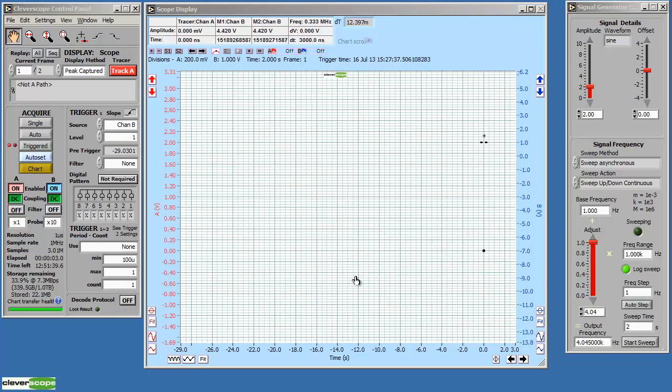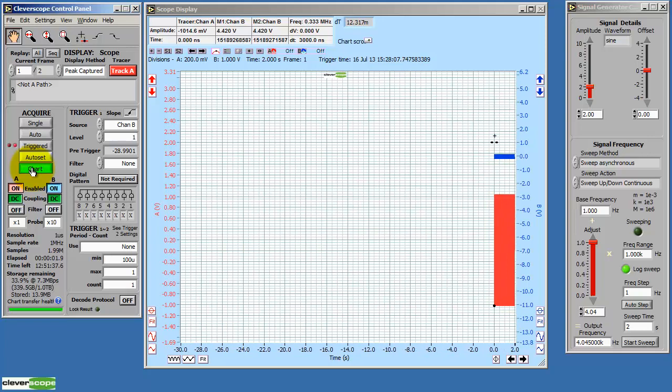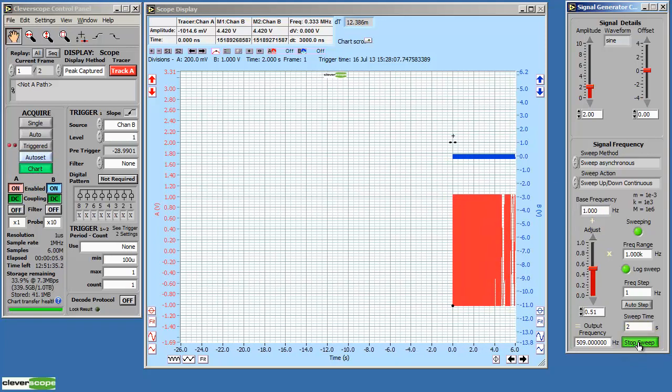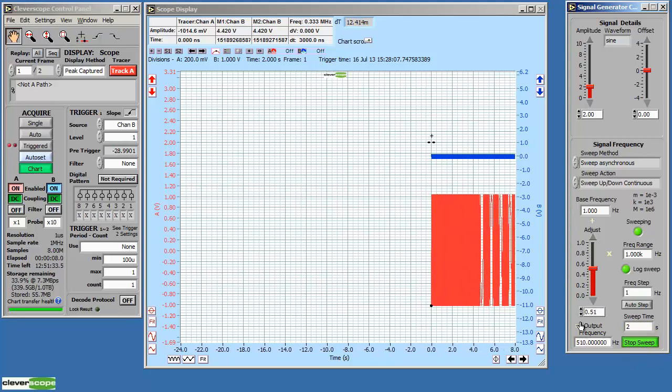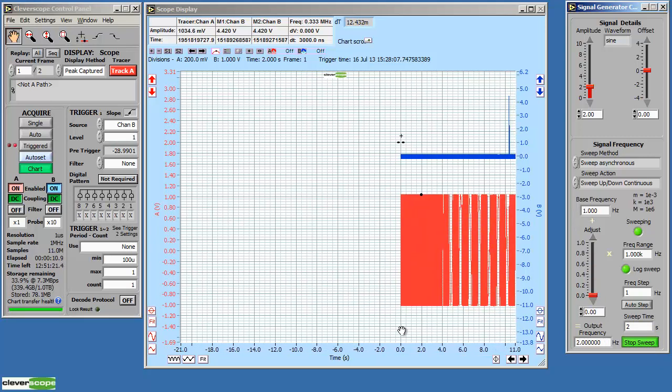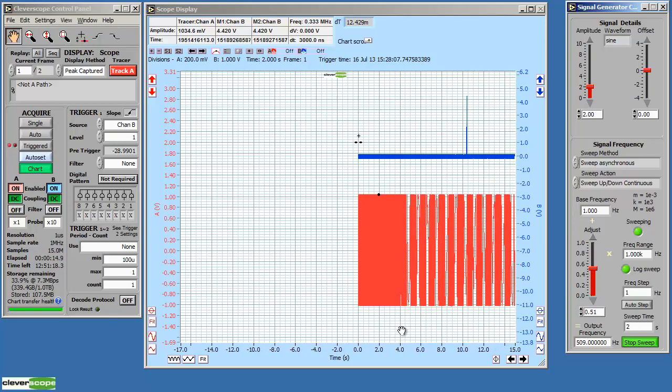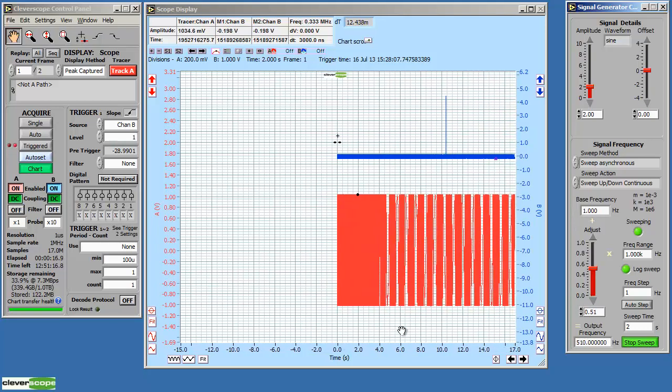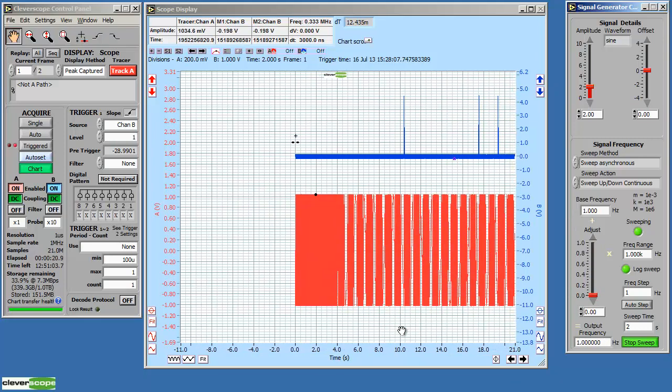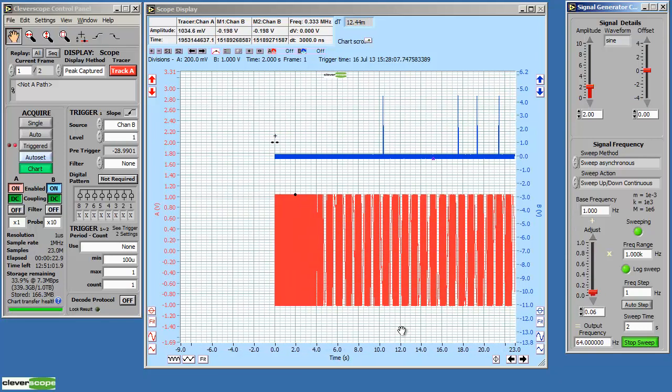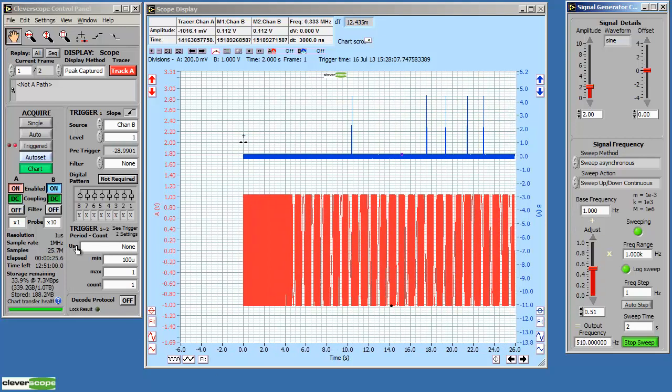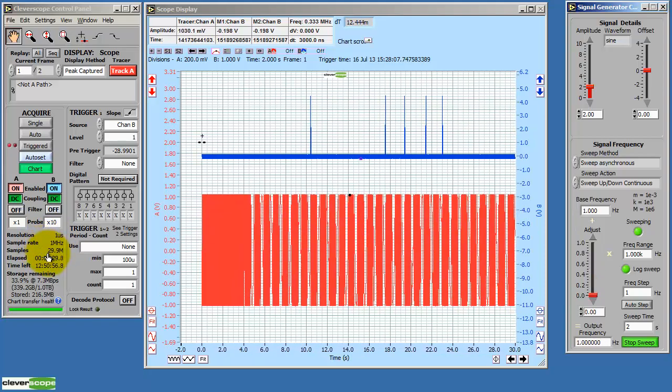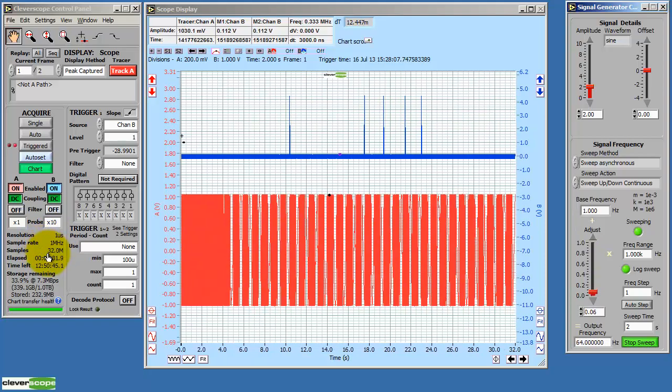Now I'm going to show you streaming to disk using the chart button. We click the chart button to start. And the scope graph starts acquiring. We'll sweep the signal generator. Now we'll press the button that made the 30 pulses. And you can see the recorded peak captured even though we're zoomed way out to many seconds. Made a few. Over here we can see that the resolution is 1 microsecond. The sample rate is a megahertz. We've sampled 30 mega samples so far.